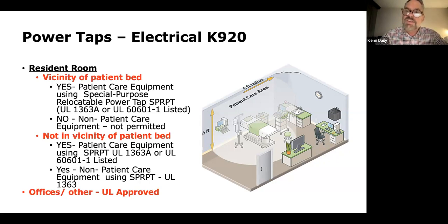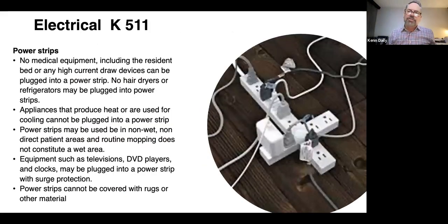And then in the offices and other parts of your building, as long as it's not medical equipment or other things we'll talk about in a second, you could use a UL approved power strip, but be mindful you can't overload them. And of course, you can use a power strip in an office, but you can't use it for heating and cooling equipment. So no hair dryers and no space heaters and no portable air conditioners. All of those things can never be used on a power strip, or an extension cord.